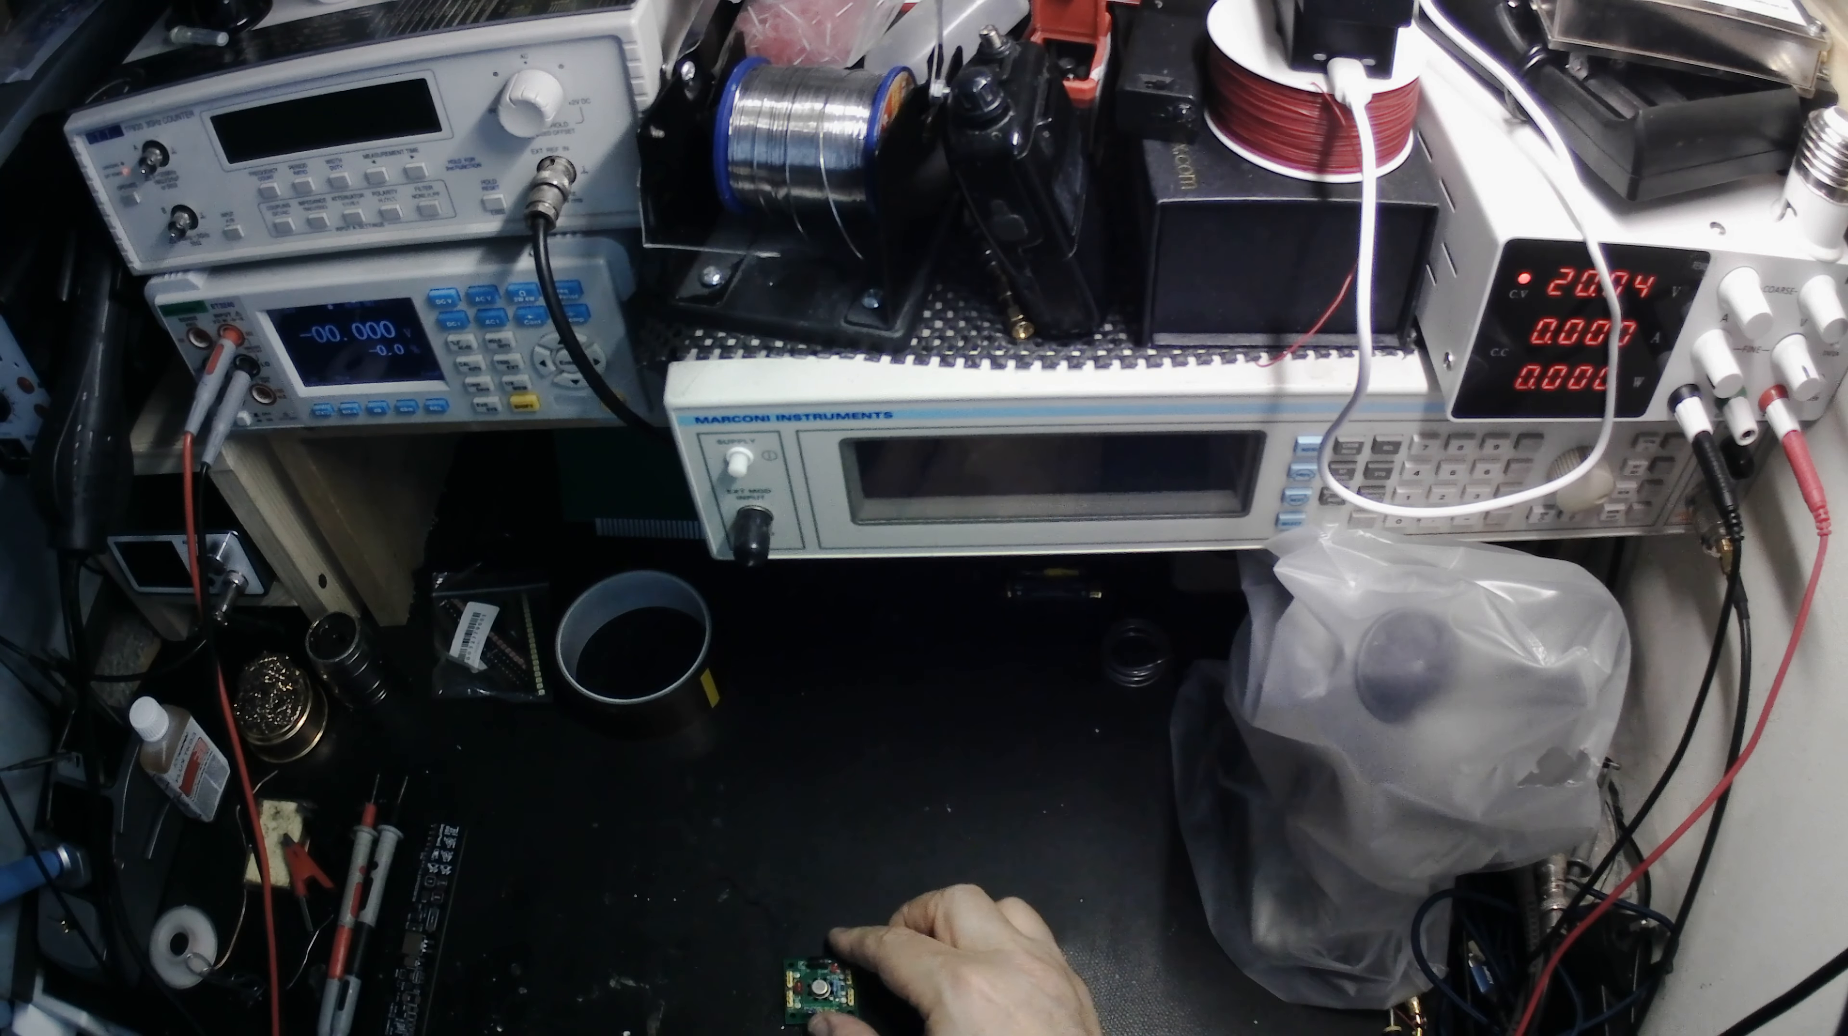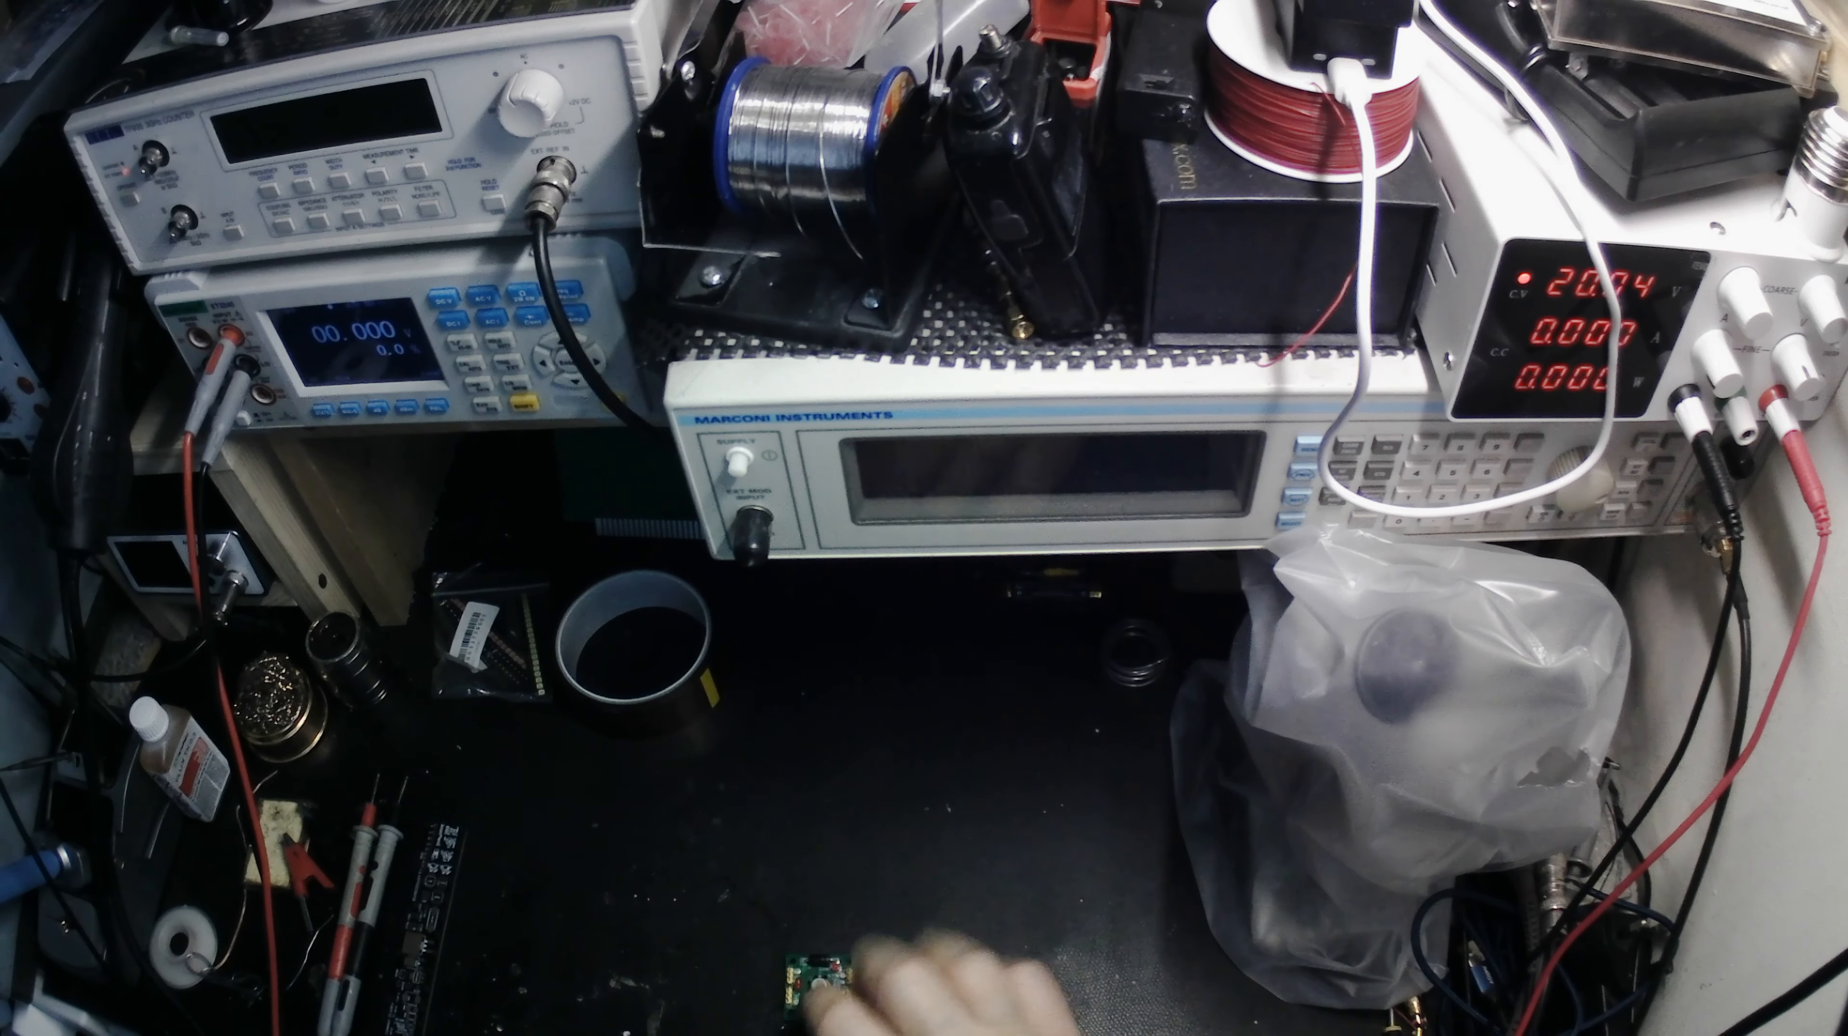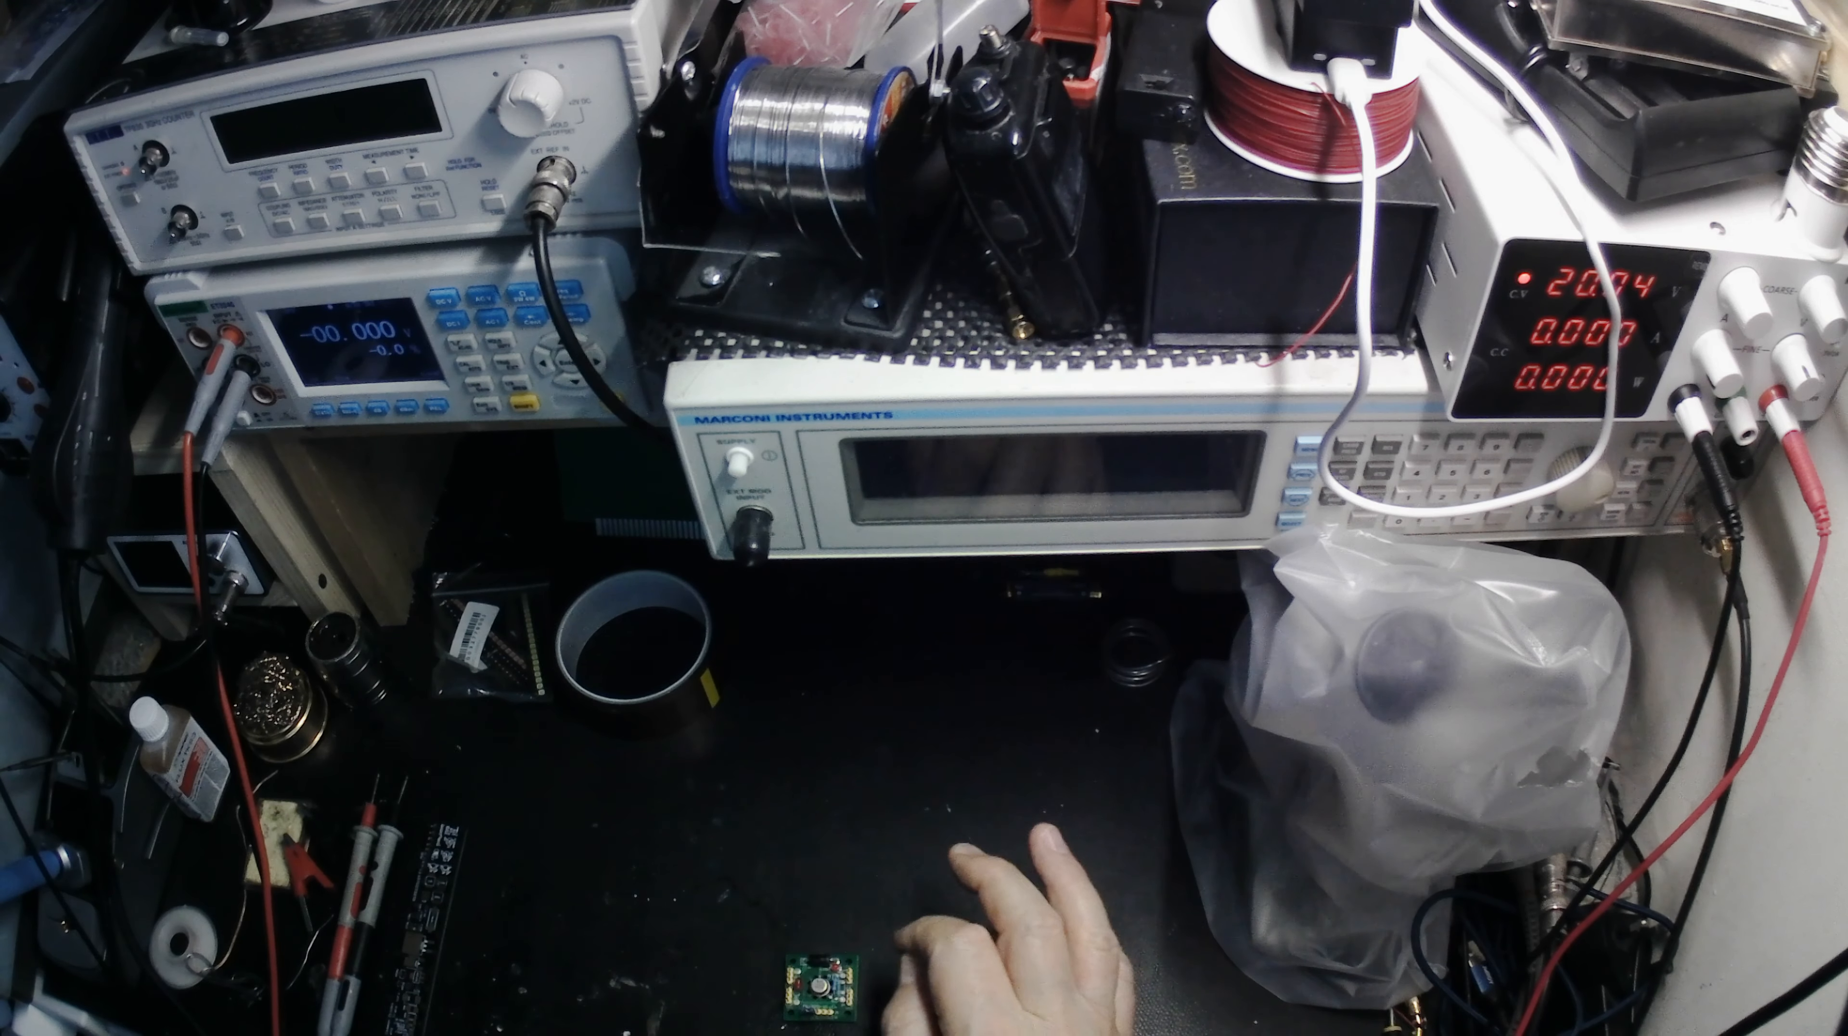But the core of this is called an AD584 and it's a precise voltage reference. So you can get, using this link, moving this link, you can get 2.5 volts, 5 volts, 7.5 volts and 10 volts at the output.